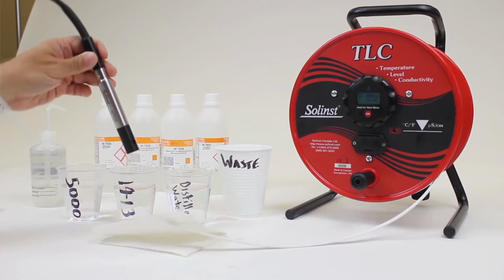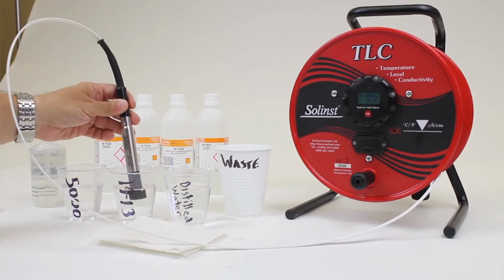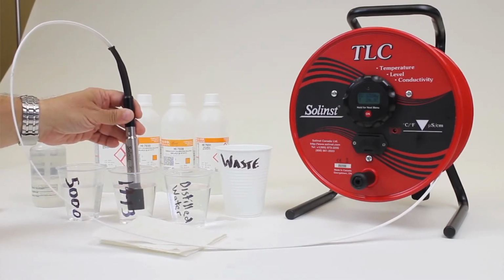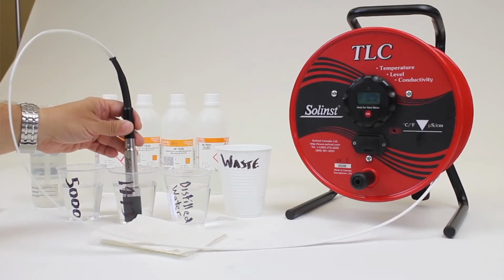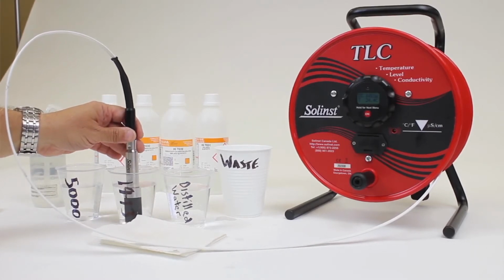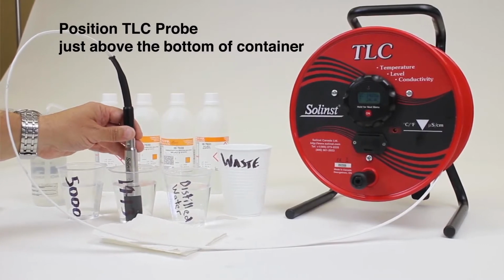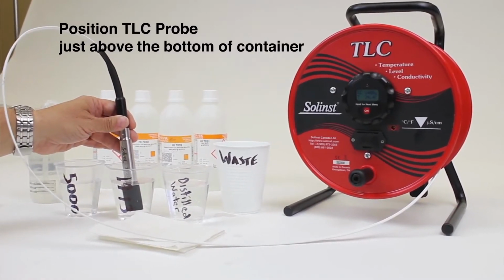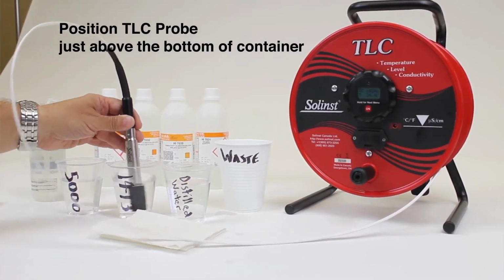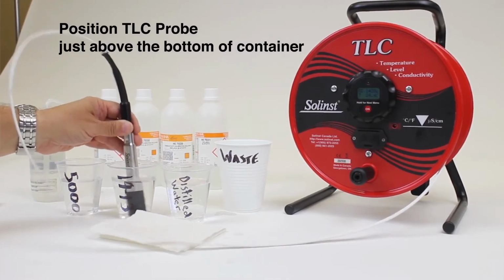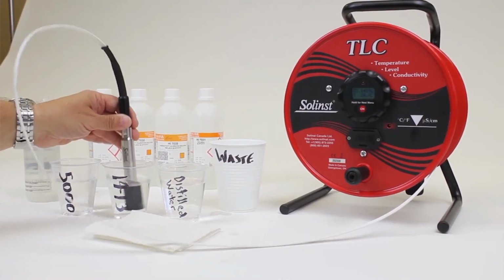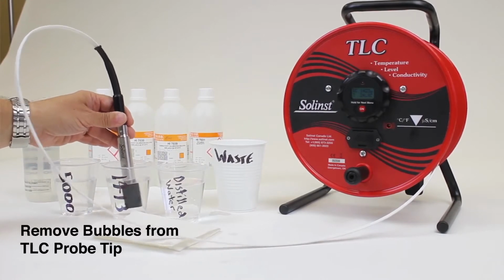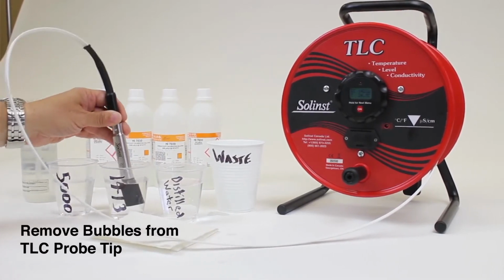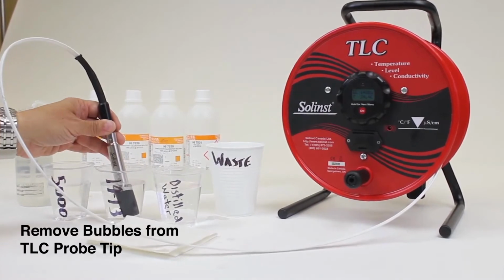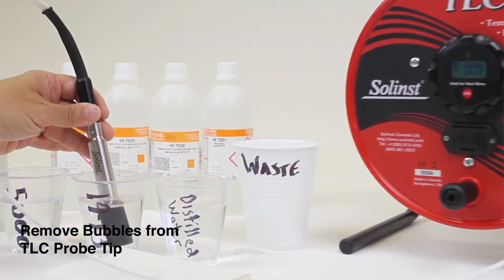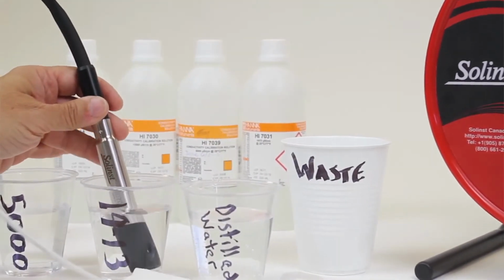So here I am starting. I'm going to put the unit in the 1413 solution. The beep just means it's gone into water. I'm never going to let it sit right at the bottom when you're doing the user calibration. You always want to maintain it a little above the bottom, and I'm going to stir it, tap it, and stir it some more to remove any bubbles that may have been lodged inside the probe. That can take anywhere from a few seconds to a couple of minutes.